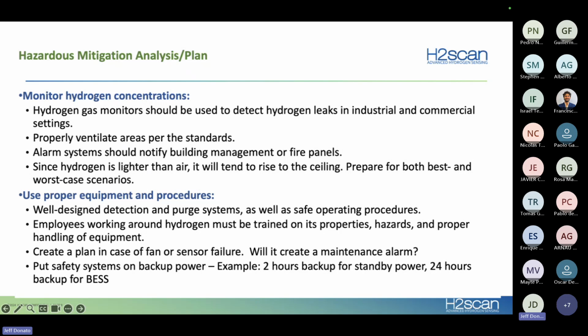So they had the charging of the battery set for 25 degrees C, but they were running the room at a much higher temperature in the middle of the aisle, so causing the batteries to gas. So there's a lot of times we have to look at monitoring, maybe not only a single point in the room, but if the room is large, we also have to monitor multiple points for temperature and maybe also for hydrogen as well. So making sure that we handle those best and worst case scenarios and have properly designed systems, properly designed airflow in the room, and of course having trained personnel.